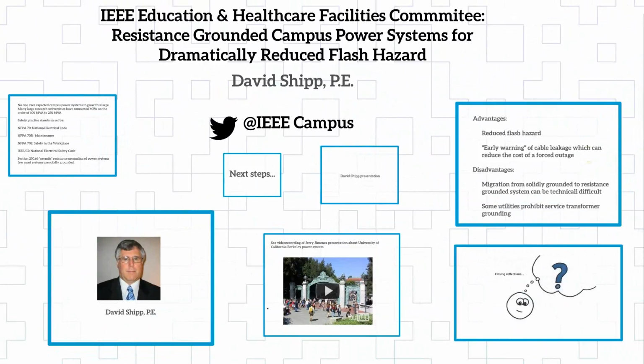Well, let me talk a little bit about what Michael and I started looking at and doing. We started this 3-4 years ago, asking what can we do in the university setting, and it's driven on multiple things. One is reliability, one is what it costs you to replace it, fix it, minimize damage, and the safety issue. Then we started going to quite a bit of different settings with Michael, and we realized that there are 2 different dimensions or systems, like the 480-volt systems, like in hospitals that are typical, or the low-voltage example, mainly because more people are in close proximity than they are going to be to 15,000-volt distribution systems, or 4160, the medium voltage levels. And really some of the requirements and the environments, the settings, and the impact on the university would be quite a bit different. So we started approaching it and broke it into 2 parts.